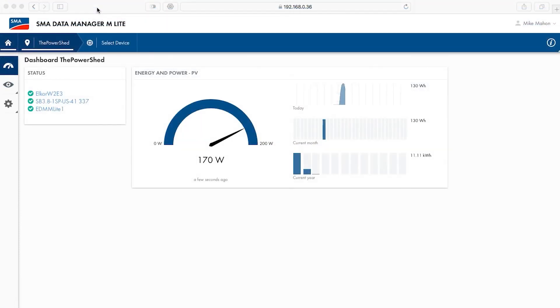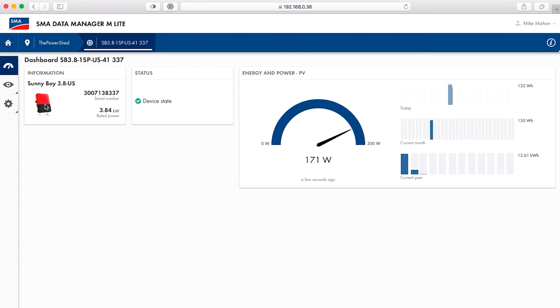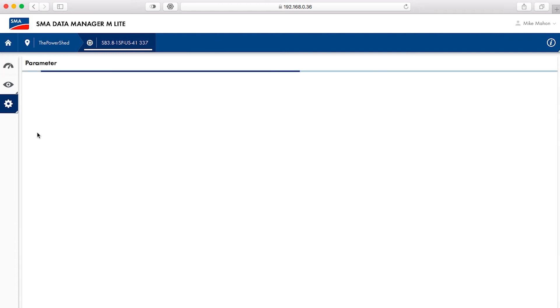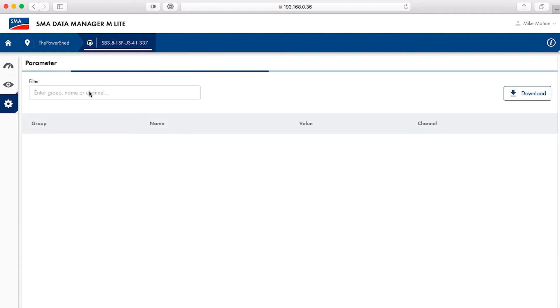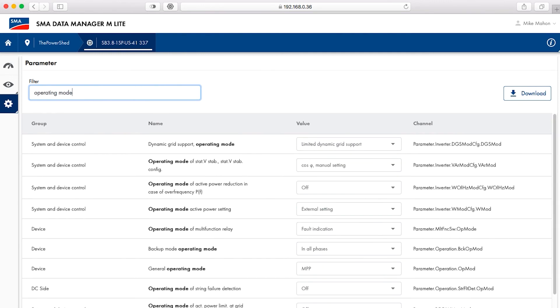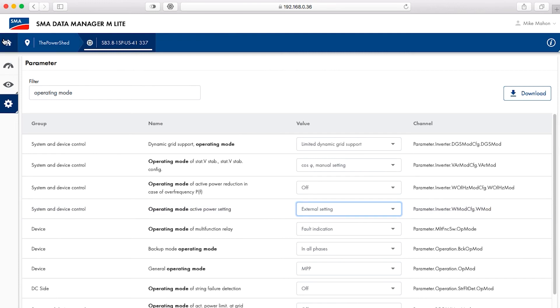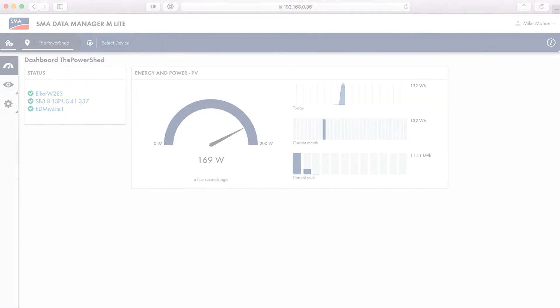It is recommended to also verify that all SMA inverters are configured to allow active power control via system communication. Select the home icon in the top left, then choose the select device item in the top ribbon to see all devices in the plant. Once the desired inverter is chosen, select the configuration icon and parameters from the list that appears. Typing operating mode in the filter window will reduce the parameters listed dramatically. Verify that the operating mode of active power setting parameter has the external setting value selected. Repeat this step for all inverters participating in the export limitation.